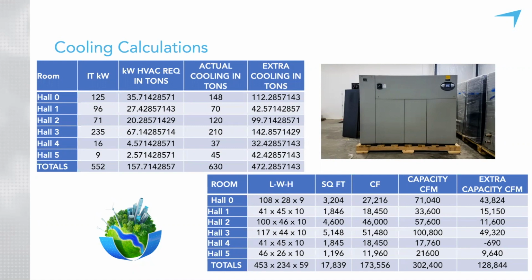But at Ohio State, our N+1 now is we have 2 20-ton CRAC units in standby. We have tested this over and over and over again. If one CRAC unit dies, it can call for the other CRAC unit to come up, or the other CRAC unit will see it. So they stay in standby mode and will come up as needed. I've seen some data center folks that have 24/7 staff where they can very quickly walk in and flip one on. I can't tell you what is best for you, but what I can tell you is here's a great way to size your cooling needs based on kilowatts.